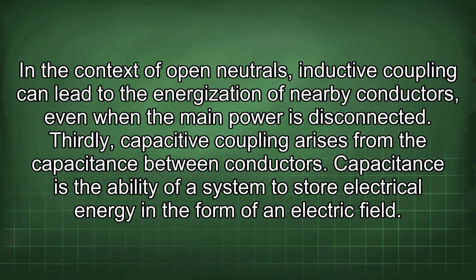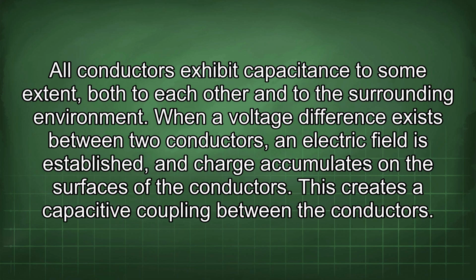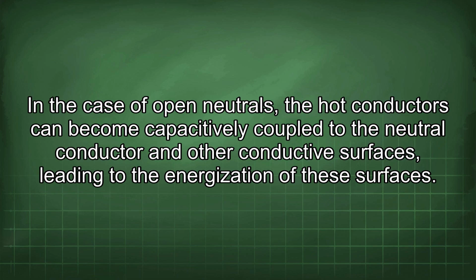Thirdly, capacitive coupling arises from the capacitance between conductors. Capacitance is the ability of a system to store electrical energy in the form of an electric field. All conductors exhibit capacitance to some extent, both to each other and to the surrounding environment. When a voltage difference exists between two conductors, an electric field is established and charge accumulates on the surfaces of the conductors. This creates a capacitive coupling between the conductors. In the case of open neutrals, the hot conductors can become capacitively coupled to the neutral conductor and other conductive surfaces, leading to the energization of these surfaces.